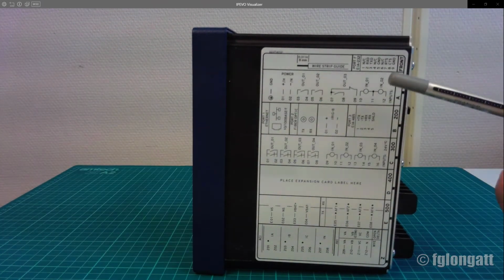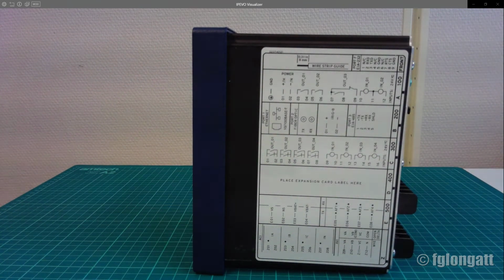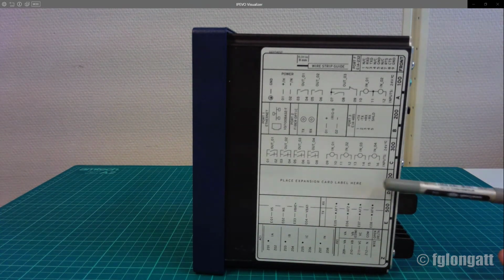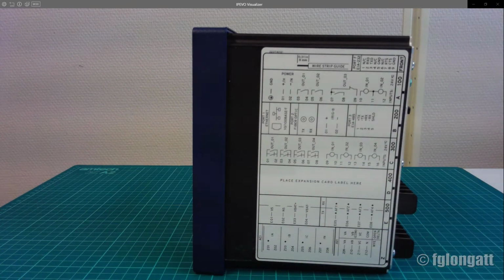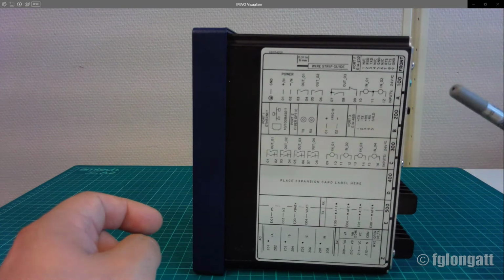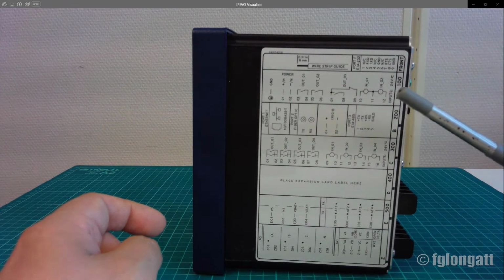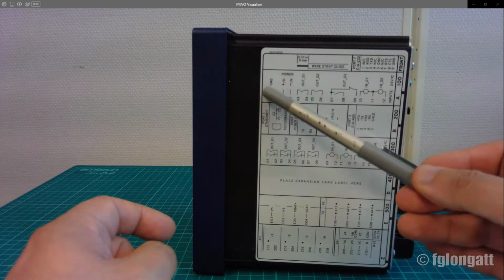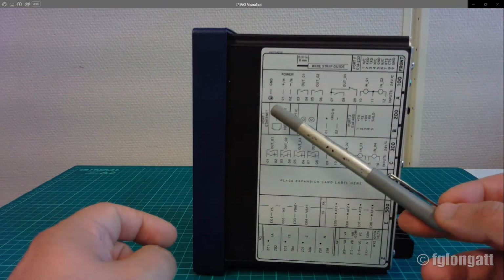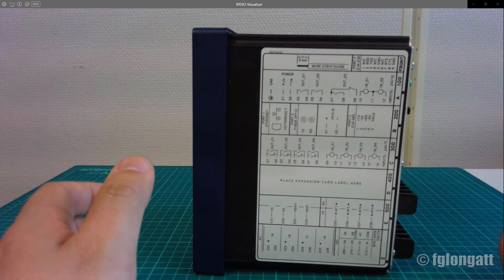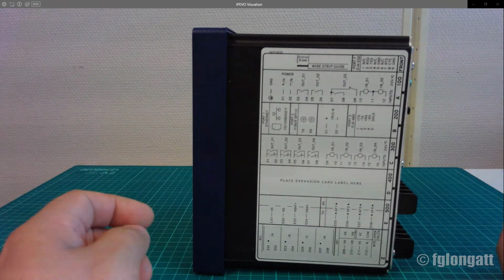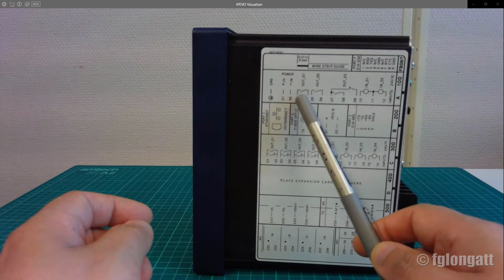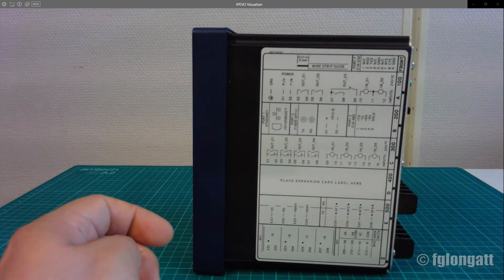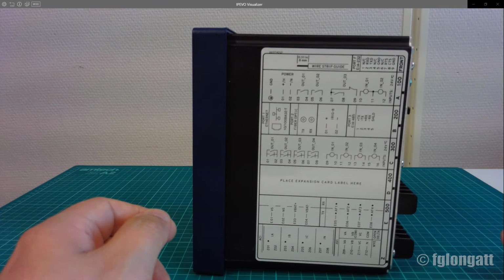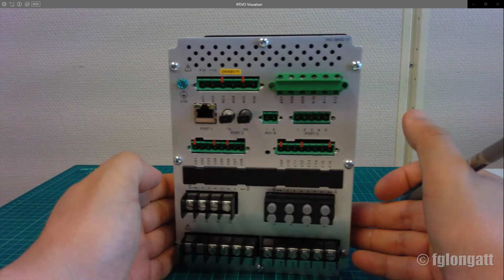Of course, there are several other cards. In this specific relay, bay D is empty at the moment, dedicated for a card label. There is a section for inputs, and also a card related to the power supply. The connector with terminals 0 to 6 represents the terminals used for power supply and interactions. Specifically, 01 and 02 of bay A are used for the positive and negative voltage that we apply for supply.